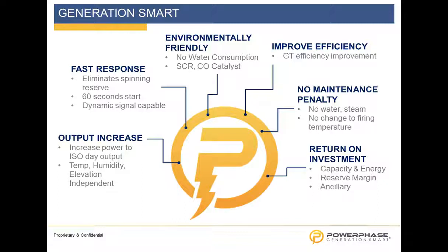We are independent of all ambient conditions. And the gas turbine turns that air into electricity at the same rate. Since we make constant air, you get constant output. And then with the fast response, as I said, we're 1 minute to start. Once we're online, we're as fast as we can move a control valve, so we're milliseconds. And that allows us to implement essentially the spinning reserve needs of the utility without actually spinning.